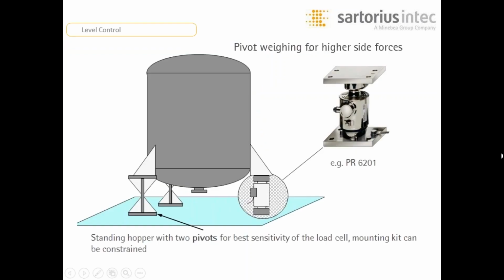Pivot weighing system level sensors can be used on 3 or 4 leg systems when incorporating pivot points on the opposite legs from the load cell. This method provides an electrical representation of the level of the tank, but it does have a much lower accuracy than a full, in this case, 3 load cell system. If the customer is looking for a 1 to 2% accuracy and just knowing the weight of the volume of product they have in the vessel, then the level by weight system will work great for them.